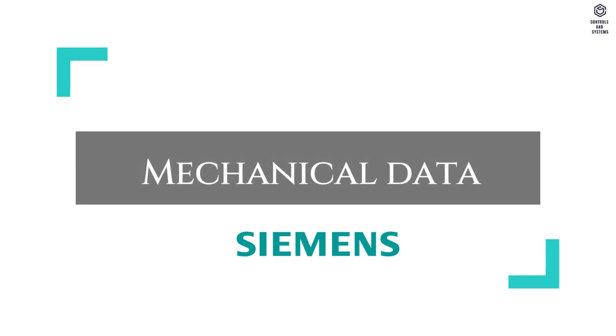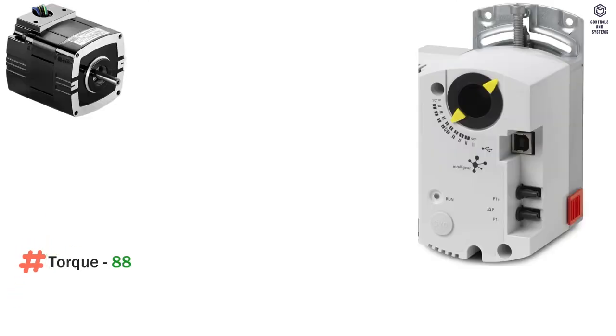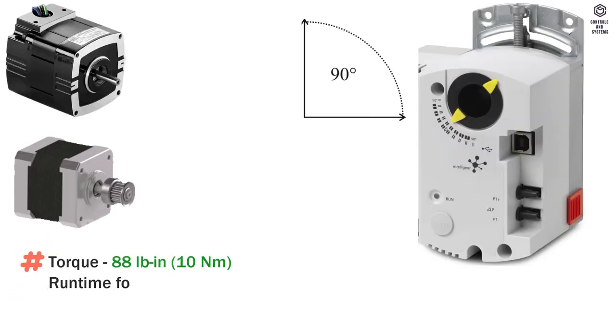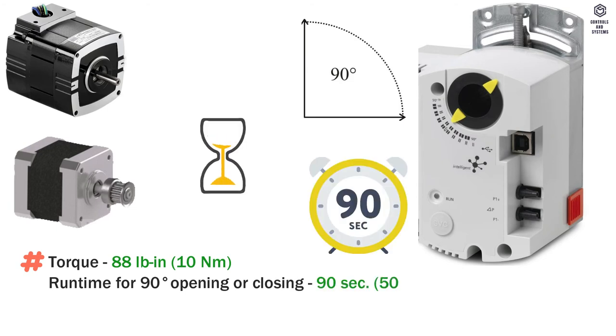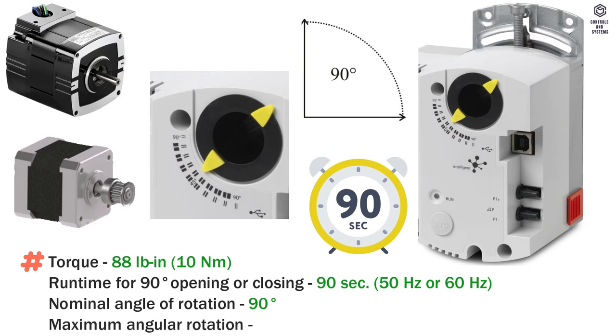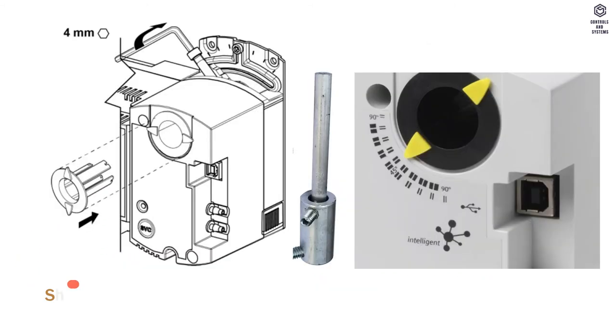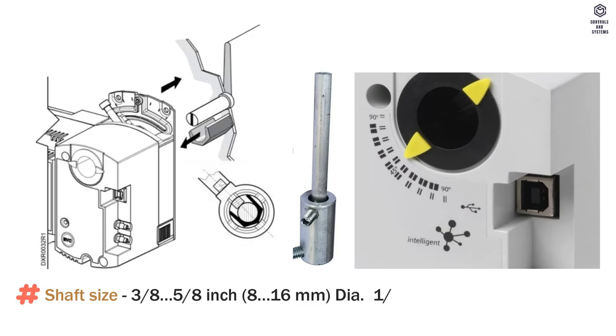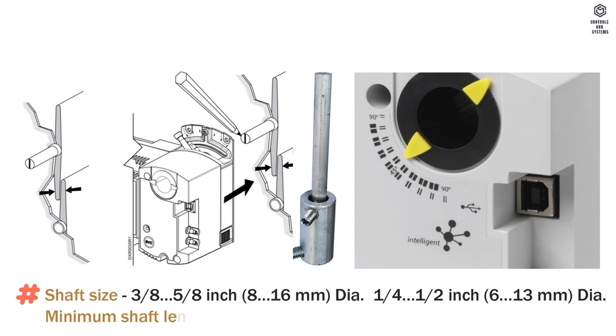Mechanical data: motor torque is 10 Newton meters. Runtime for 90-degree opening or closing is 90 seconds. Nominal angle of rotation is 90 degrees. Maximum angular rotation is 95 degrees. Shaft size is 8 to 16 mm and 6 to 13 mm. Minimum shaft length is 20 mm.